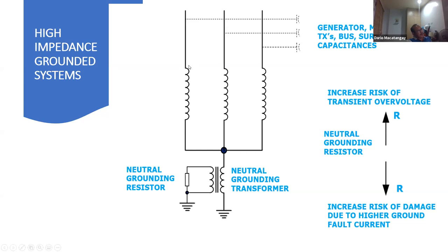here, if you have a fault here, this voltage here is now connected to ground, okay? It's shorted here, right? So if it is shorted here, this voltage will become almost zero. And the voltage here will increase to almost line to line. This is almost line to line. But the voltage that was present here from line to neutral will shift here. This will be like 13,800 volts, okay?